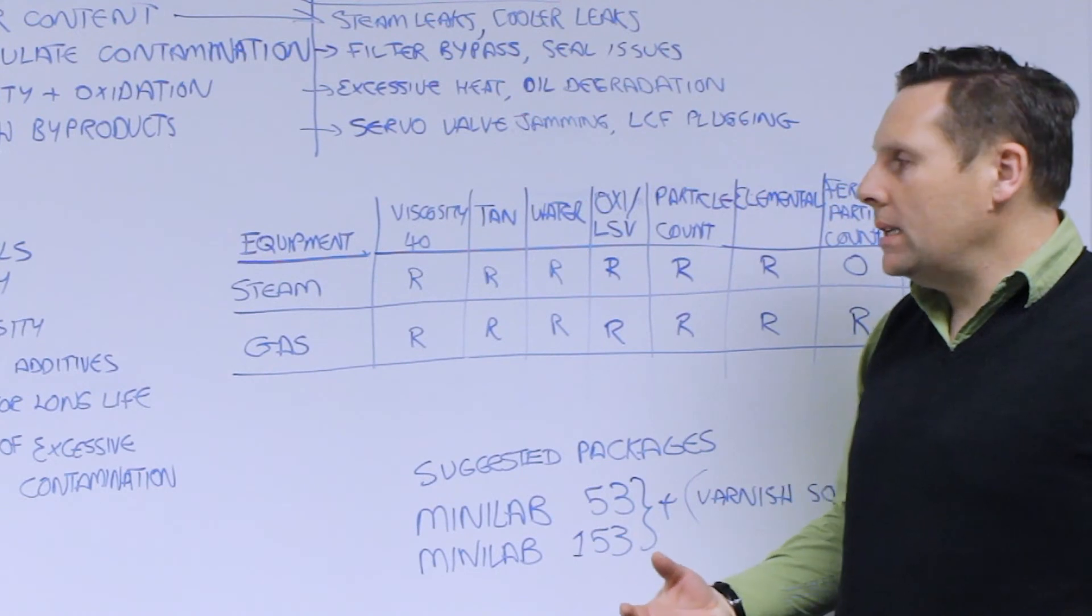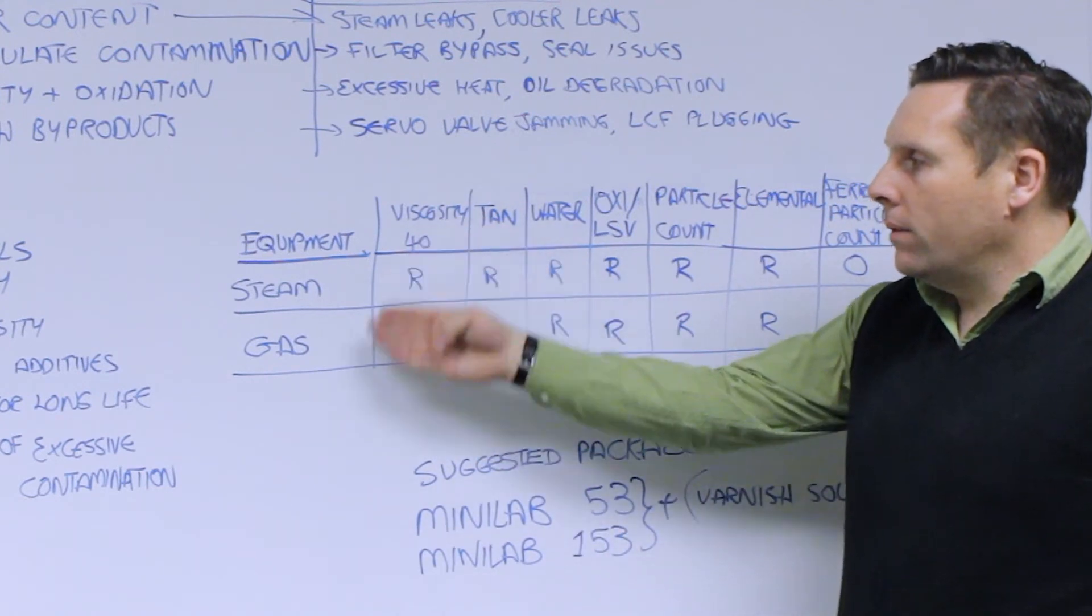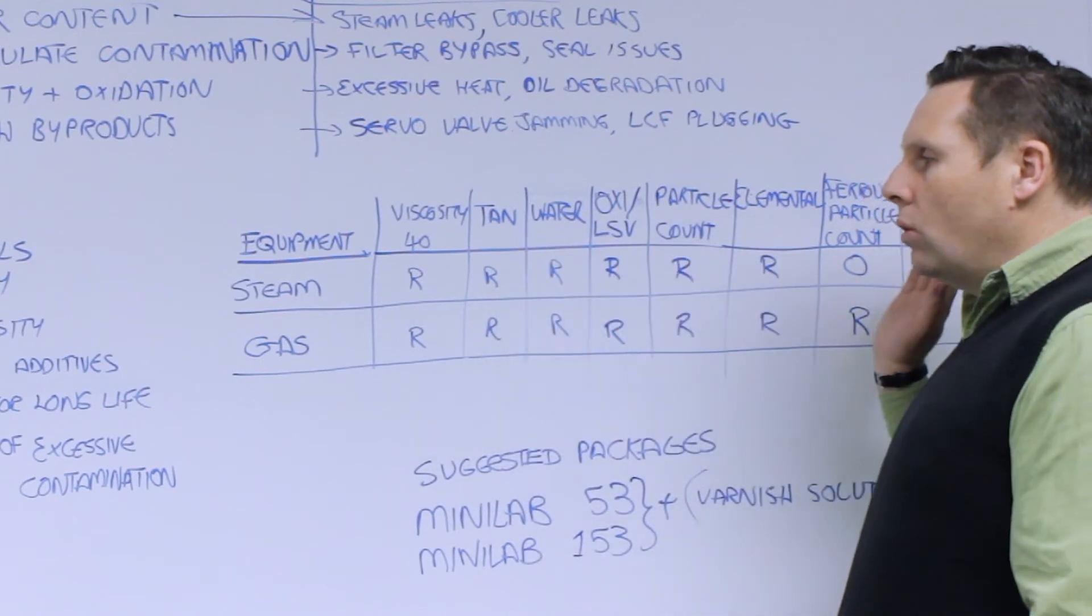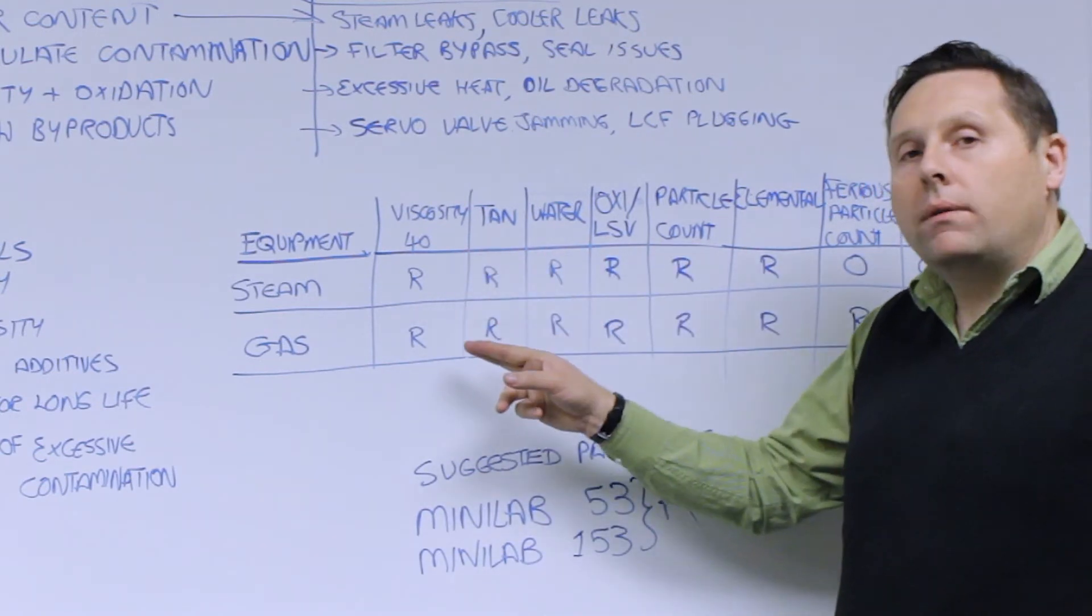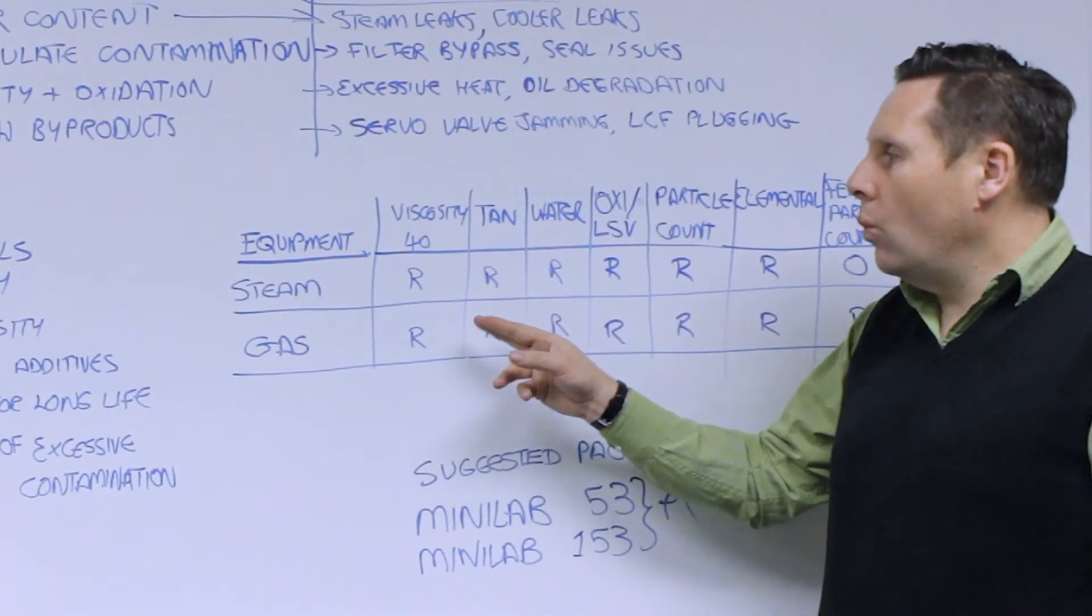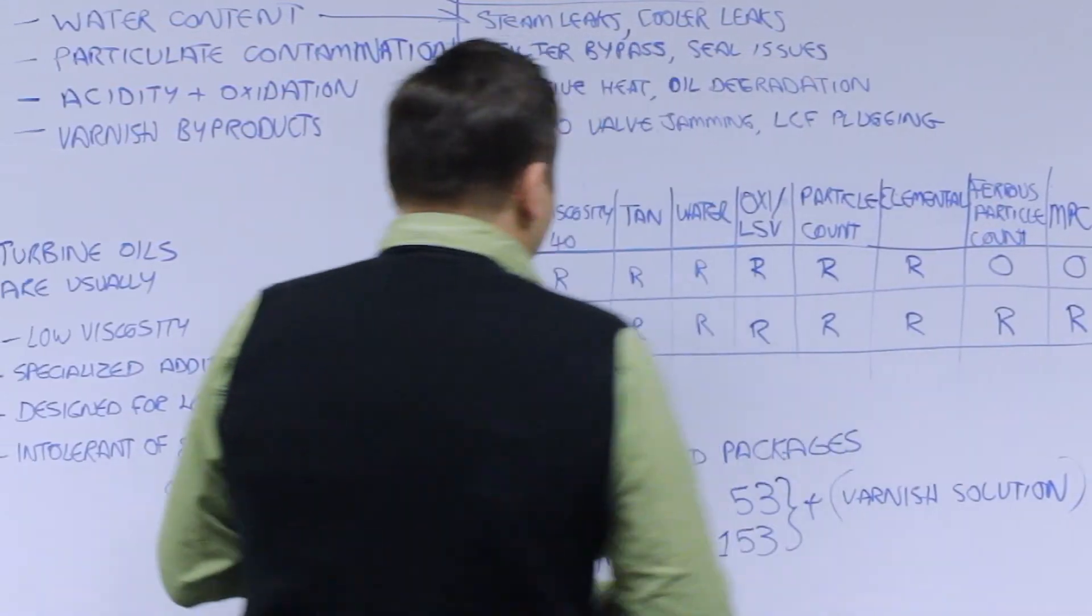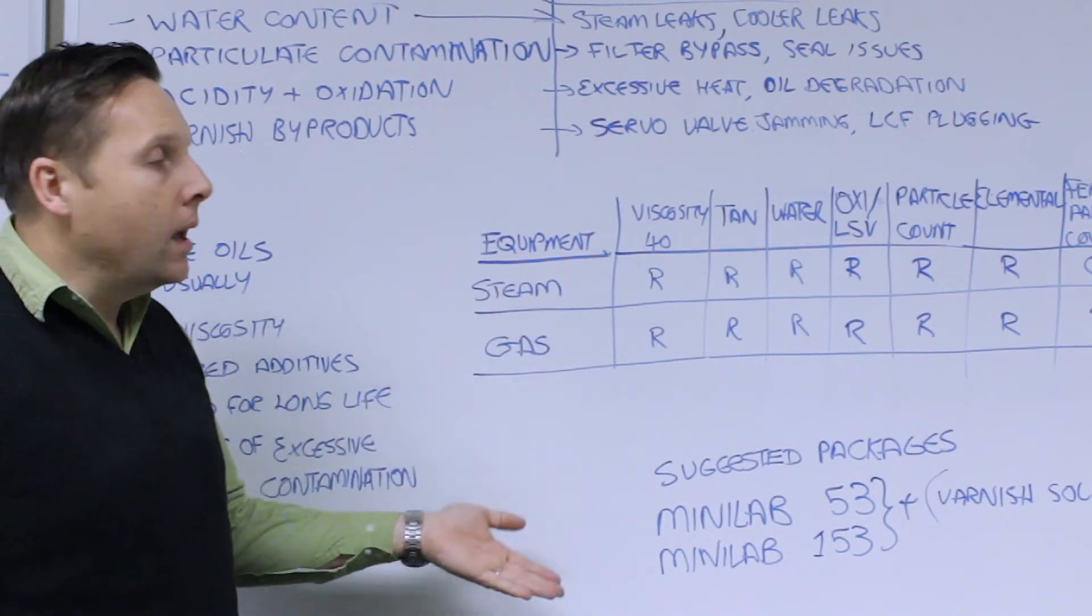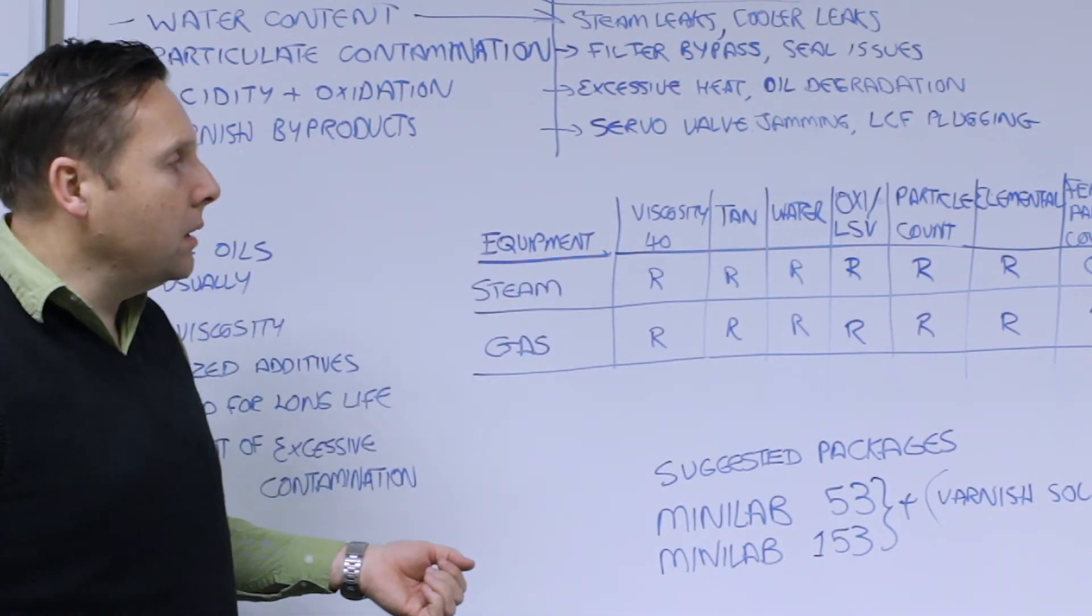So as a result of that, what are the key tests that we want to monitor? Well for the most part steam and gas are pretty much the same but let's really go over the key areas. We want to look at viscosity. Why? Because viscosity is the most important physical property and it's indicative of lubricant film strength to maintain that hydrodynamic pressure on the bearings.